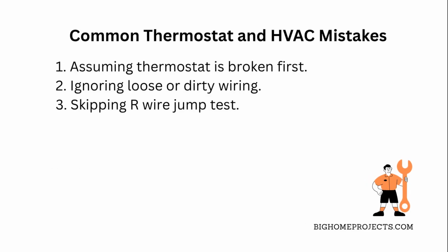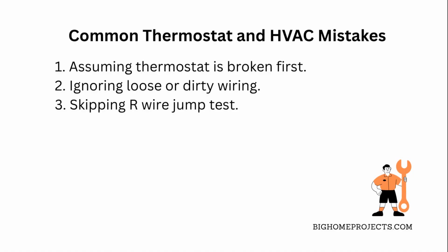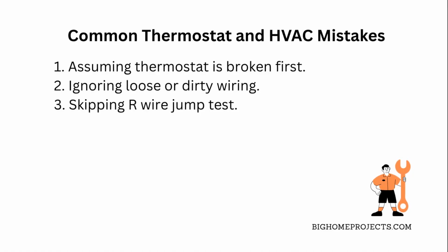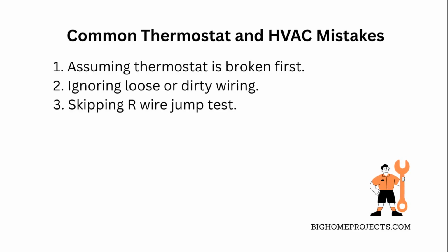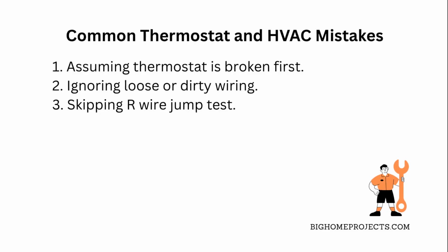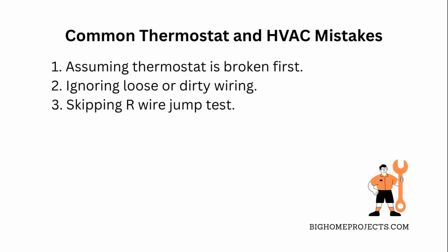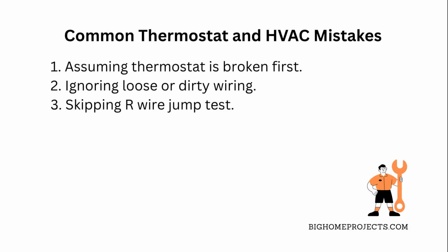One of the biggest mistakes when troubleshooting thermostat and HVAC problems is assuming the thermostat is broken without testing voltage first. This leads to unnecessary replacements. Fix that by always using a multimeter to check for 24 volts before swapping parts. Another common slip-up is ignoring wiring issues like loose or dirty connections that can stop signals from getting through. Tighten and clean those terminals before blaming hardware.